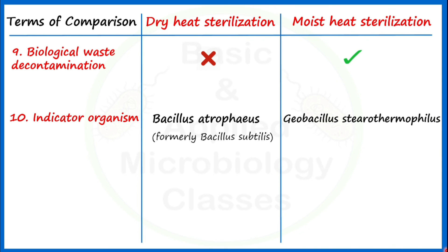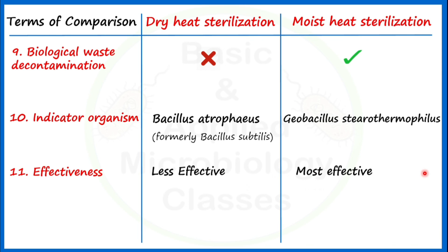The eleventh point of difference is effectiveness. Dry heat sterilization is less effective, while moist heat sterilization is most effective. This is judged based on the time and temperature combination used — moist heat uses lower temperature and less time to achieve sterilization. However, both techniques are important in practice, as certain materials can only be sterilized by one or the other method.